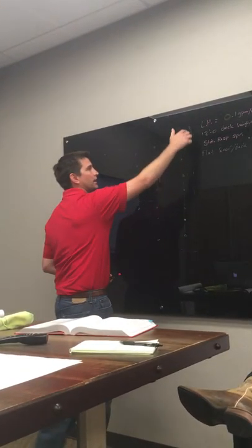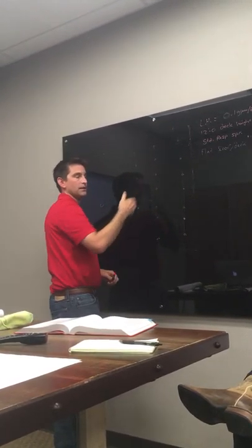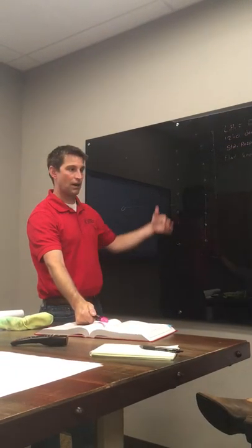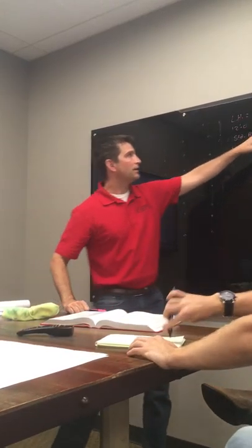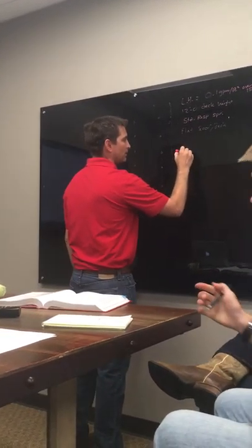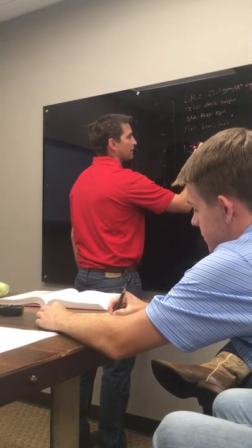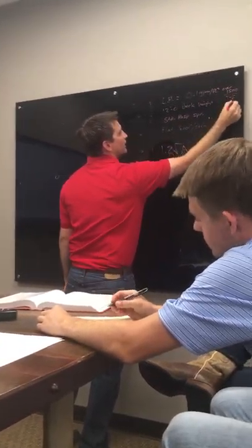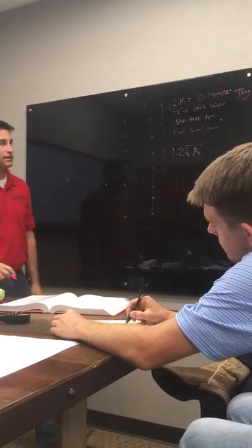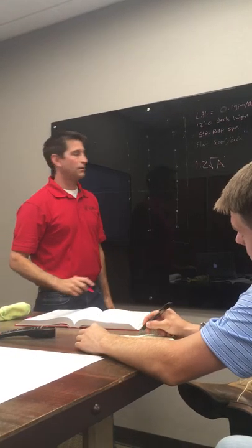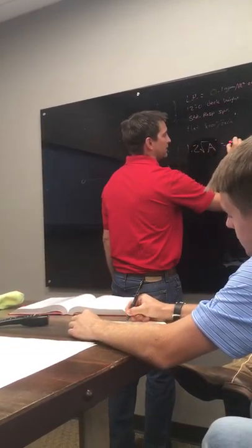So we're actually going to do our rectangle the long way here. Then there's an equation to make your life even easier that says, how far do I have to go? Well, it's based on your remote area size. Okay? So here you go, write this down: 1.2 times the square root of your area. When I say your area, that's your design area, whatever it currently is. In our case, we have standard response sprinklers, it's 1,500.